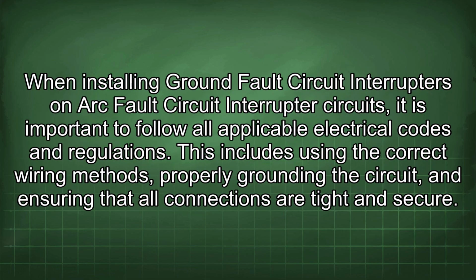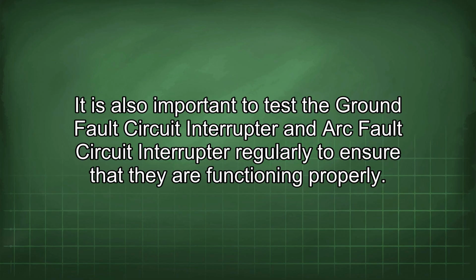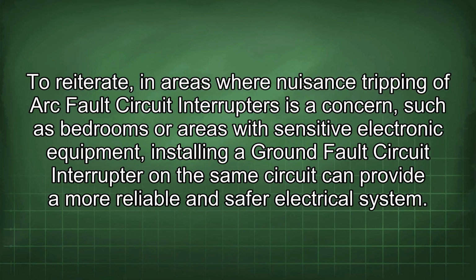By having both types of protection in place, you can significantly reduce the risk of both electrical fires and electrical shocks. When installing ground fault circuit interrupters on arc fault circuit interrupter circuits, it is important to follow all applicable electrical codes and regulations. This includes using the correct wiring methods, properly grounding the circuit, and ensuring that all connections are tight and secure. It is also important to test the ground fault circuit interrupter and arc fault circuit interrupter regularly to ensure that they are functioning properly. To reiterate, in areas where nuisance tripping of arc fault circuit interrupters is a concern, such as bedrooms or areas with sensitive electronic equipment, installing a ground fault circuit interrupter on the same circuit can provide a more reliable and safer electrical system.